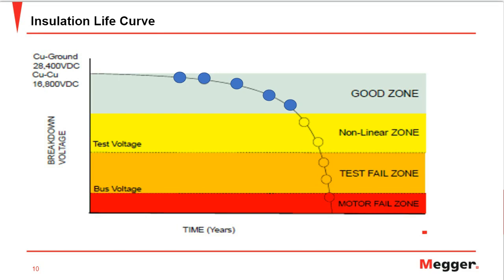Without predictive testing, the motor failure will come without foreknowledge if we just perform low voltage testing, which usually happens at this bus voltage level. So what we are trying to focus on is the yellow zone, the non-linear zone, and the test fail zone. With predictive testing, we determine if our motor lies in this zone, or if there is some incipient failure that would result in motor failure in future, which would of course save us a lot of unscheduled downtime. Just repeating it again: to find the problems up here, we need to test in the yellow zone and the orange zone, which is the high voltage testing. And there are various insulation failures. We'll discuss the major ones, which the DC high potential or the surge testing covers.